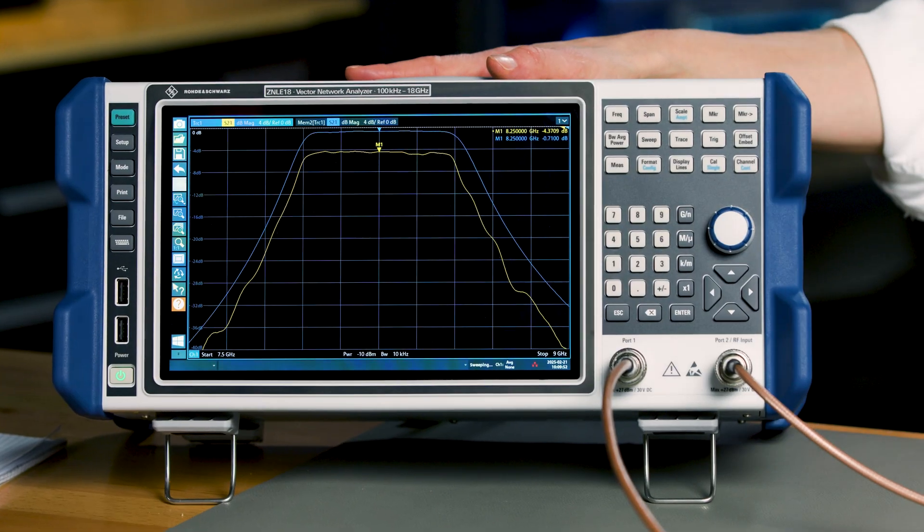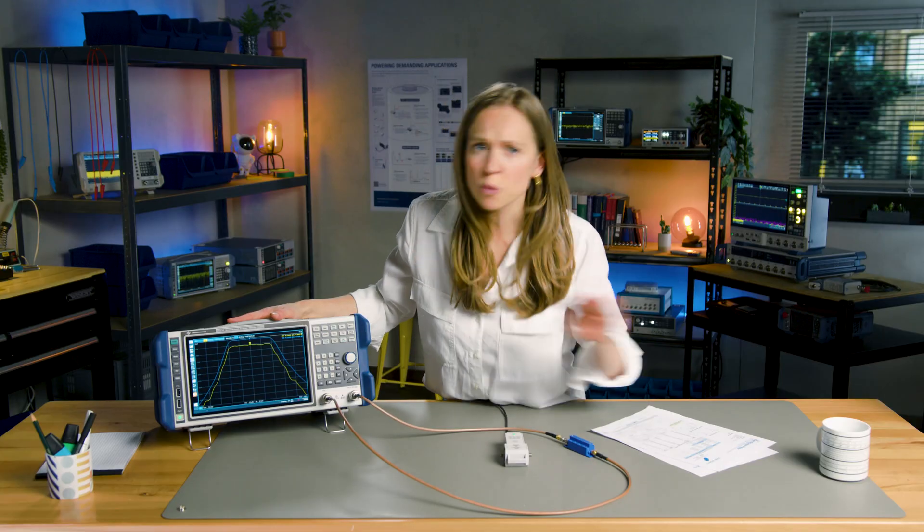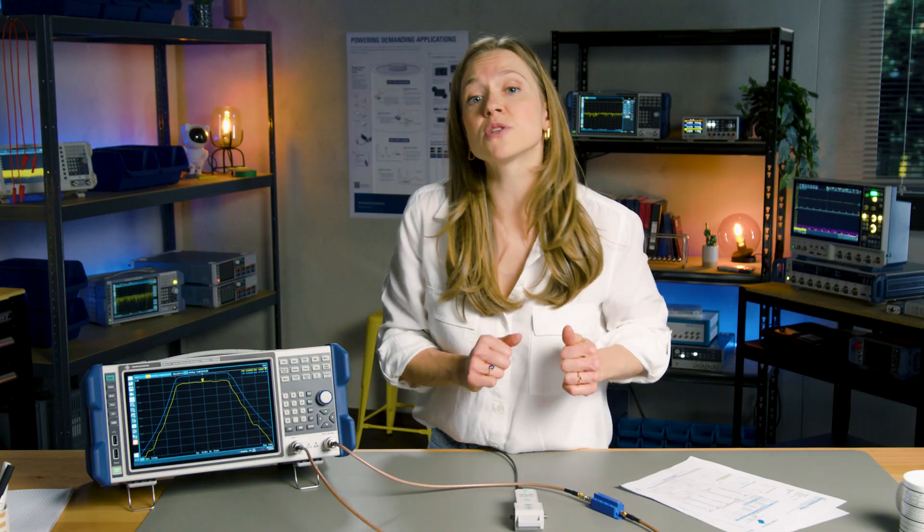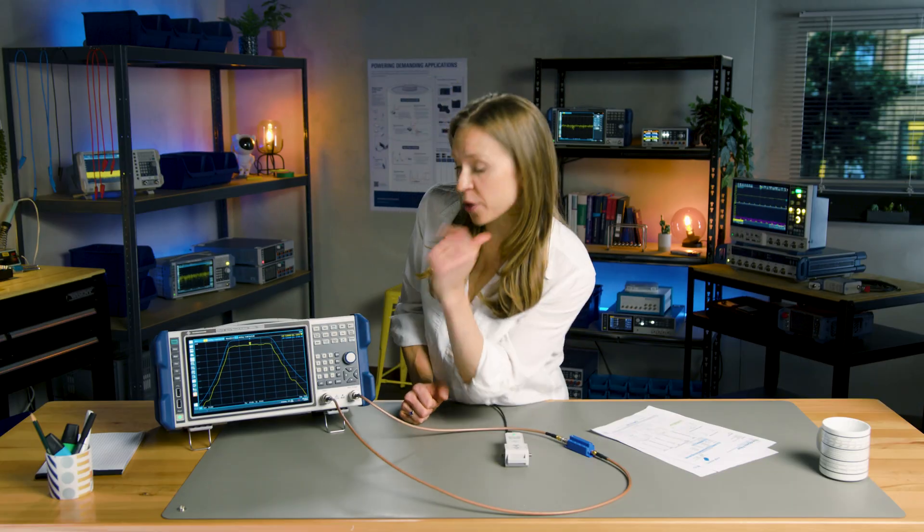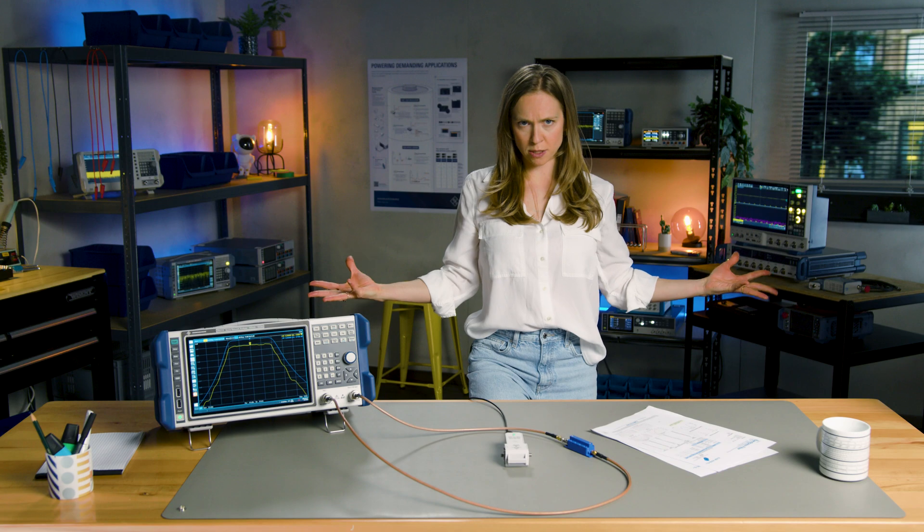Now, let's set up our VNA. For a first quick measurement, we do it without user calibration. We'll come to that point later. We'll begin with a frequency sweep up to 9 GHz to capture the overall response.